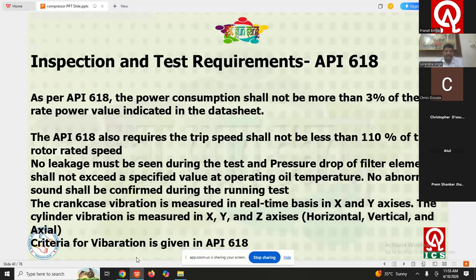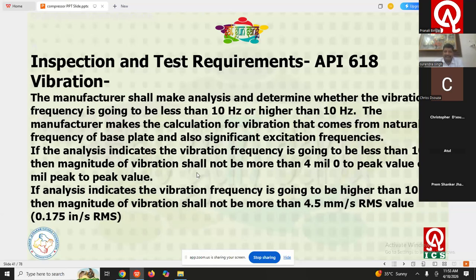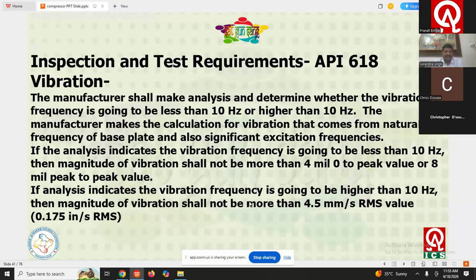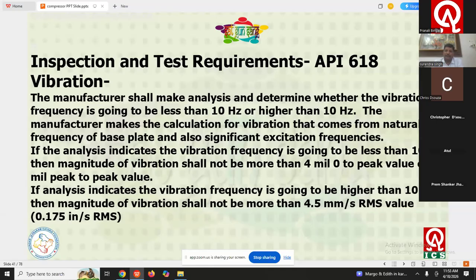So this is the criteria given in API 618 for vibration: first the vendor will identify the frequency, and then if the frequency is higher than 10 hertz, the magnitude of the vibration shall not be more than 4.5 mm per second. How we can check the vibration, I will brief in the upcoming slides. The document I showed, you can check through the instruments.